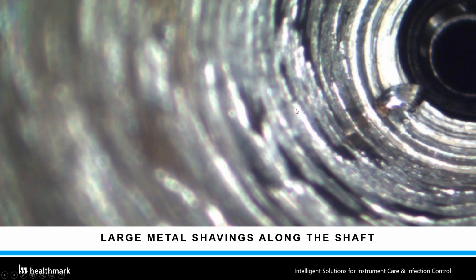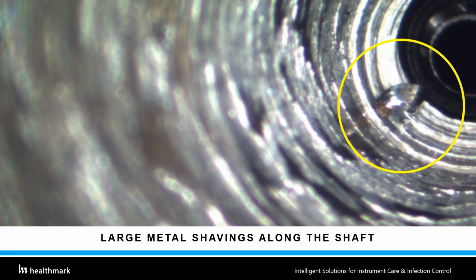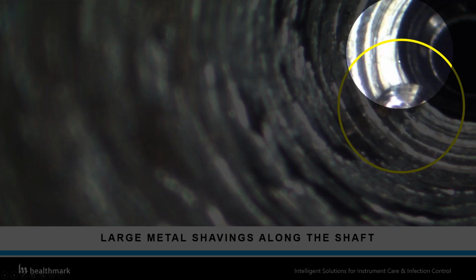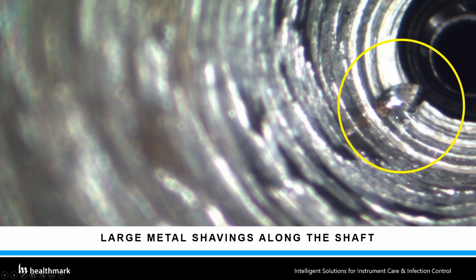And one more, which is interesting: you see that there's a piece of shaving that was attached to this. My assumption was that if you put this through the normal washing, it would come out, but it didn't, for two reasons. One, obviously, when they were shaving, it was hot and got stuck in this area. And the other part was that it didn't come out no matter what we did. We brushed it and ran it through the normal process, and this shaving piece didn't come out. That was really interesting, because we were buying these brand new, medical devices from a well-known manufacturer, and here we have a defect on something that you don't assume you need to look into.